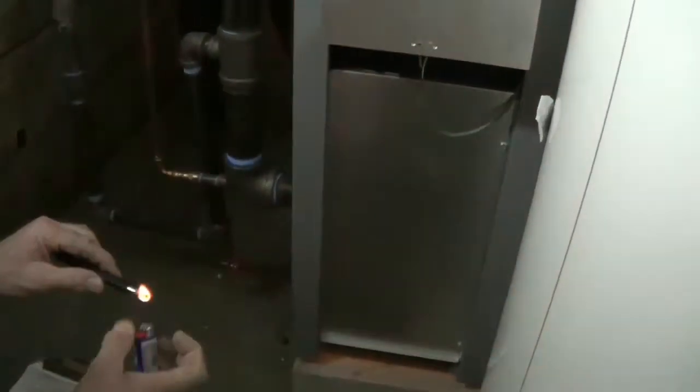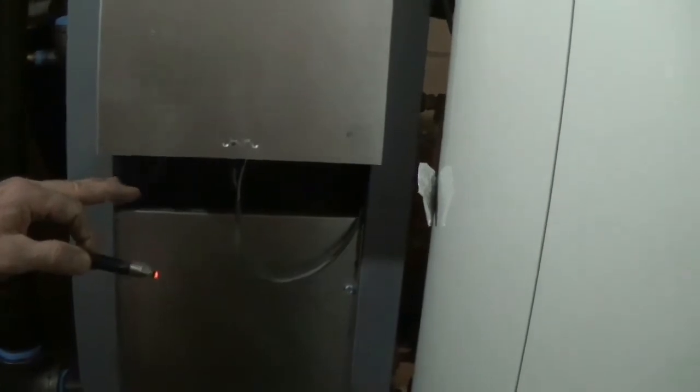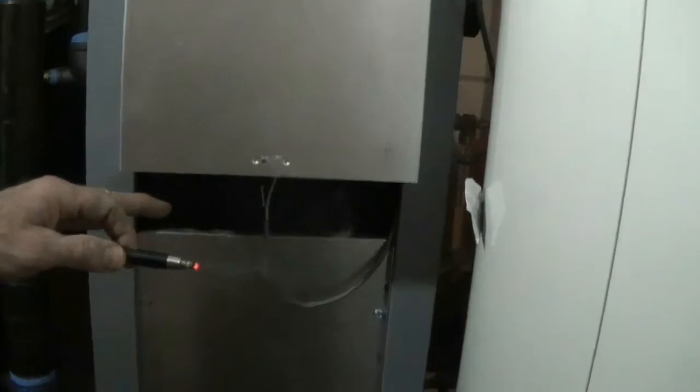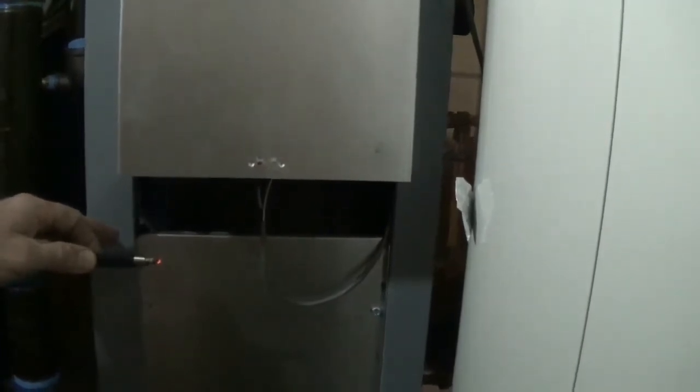We hold this down below the line right at which that box, which we call the draft hood, is. I'm right under it, and you can see the smoke is getting pushed out. I can also feel with my hand that there's hot exhaust gas pushing down against me. That should not be happening. The flue gases should be going up the chimney, and I should feel cool air going by my hand on the way into this box, and that's not happening. This is spilling like crazy. So we can go for another 40 seconds.